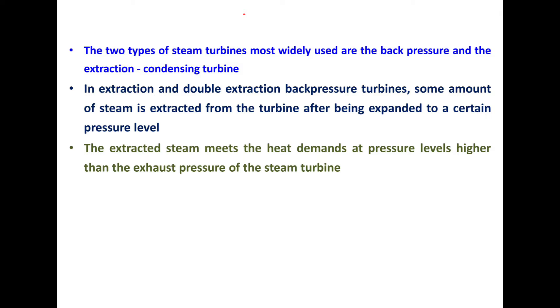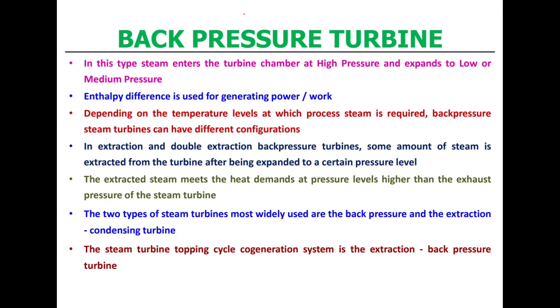In extraction and double extraction backpressure turbines, some amount of steam is extracted from the turbine after being expanded to a certain pressure level. The extracted steam meets the heat demands at pressure levels higher than the exhaust pressure of the steam turbine. In the backpressure type, steam enters the turbine chamber at high pressure and expands to low or medium pressure. The enthalpy difference is used for generating power or work. Depending on the temperature level required, backpressure steam turbines can have different configurations.